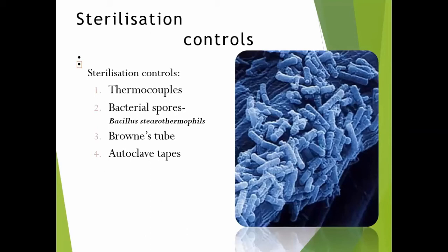Sterilization control. Here we can also see a picture of sterilization control. The sterilization controls include thermocouples, bacterial spores, Bacillus stearothermophilus, Browne's tube, and autoclave tapes.